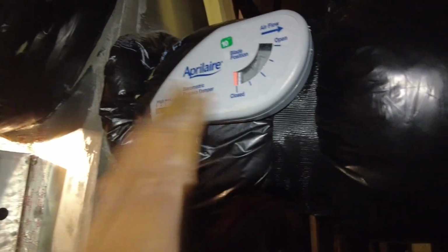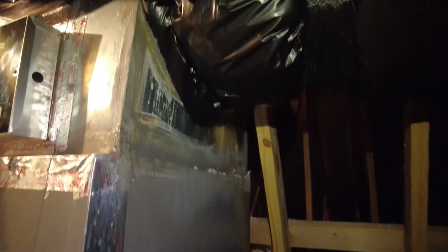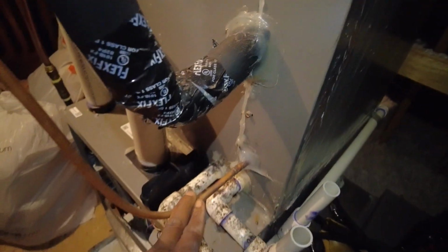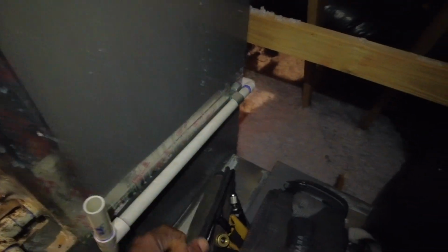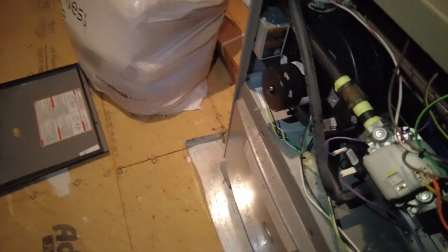And I'm going to do that with this one as well. And it's going to help with not necessarily utilizing this bypass anymore, because like I said, we don't really like the bypass in the Carolinas here, and if the system's not really set up for it properly, if the ductwork's not set up for it properly, we don't want to utilize that. Yeah, it does have a TXV that will help. Definitely don't want them with a piston-driven metering device, because otherwise that superheat might not get governed properly. But yeah, we're looking pretty good.